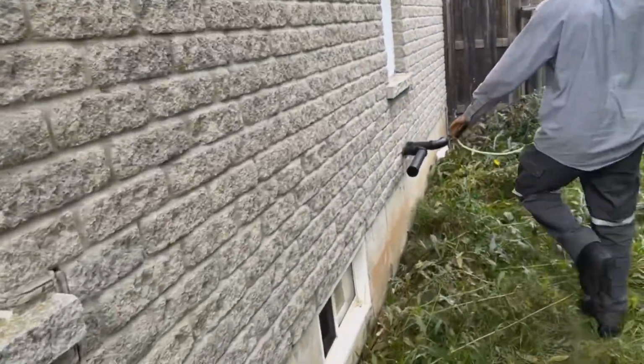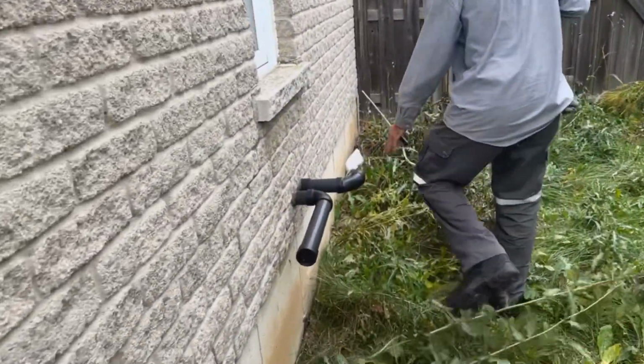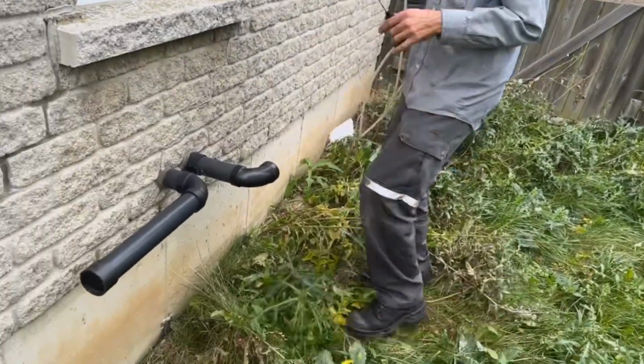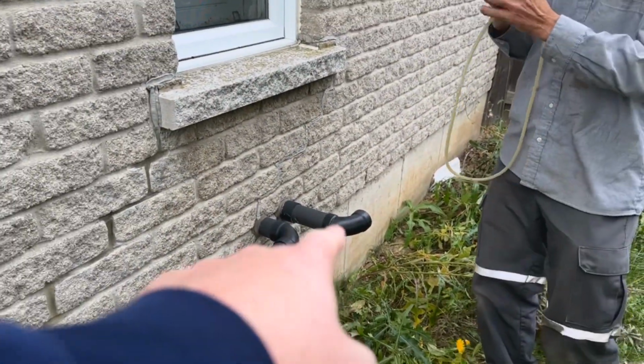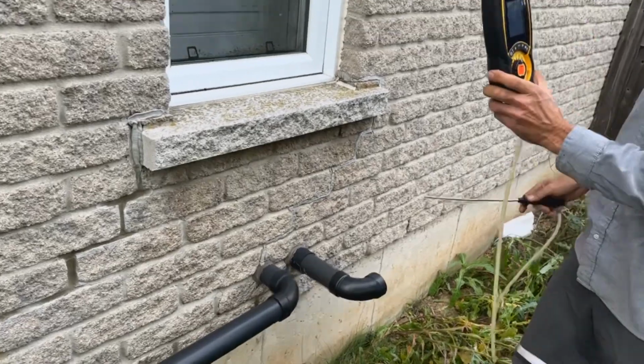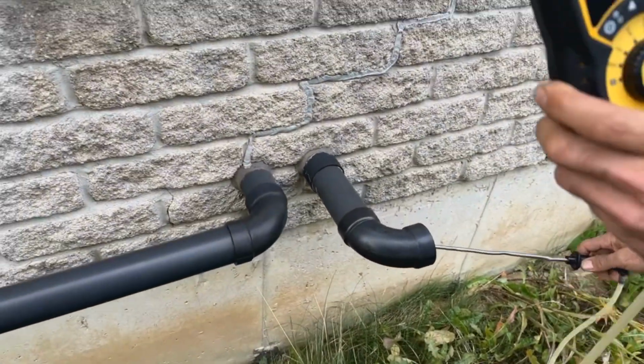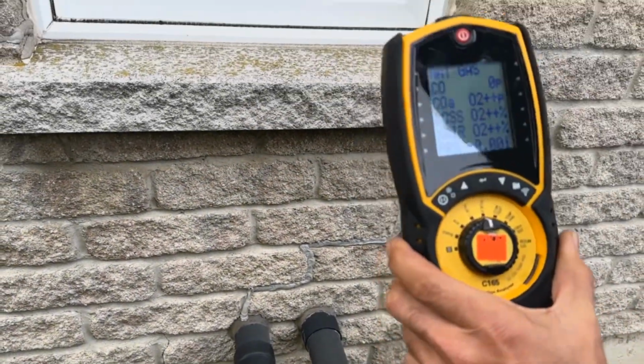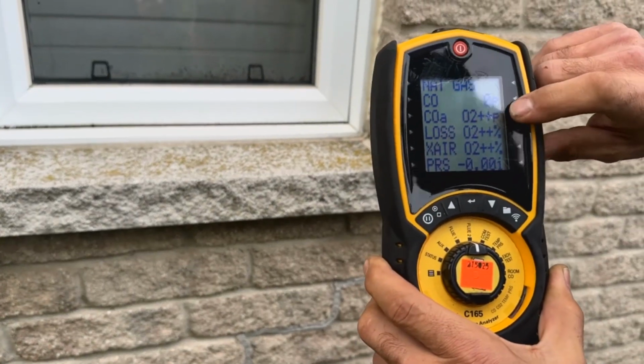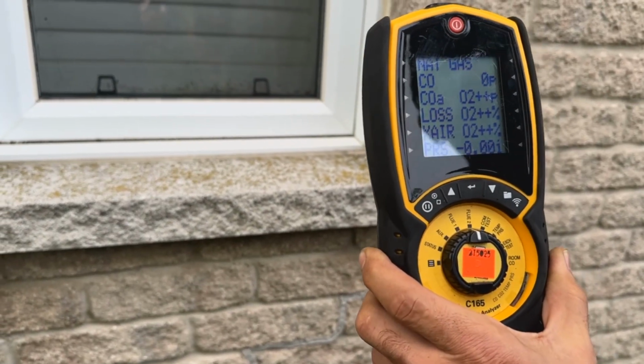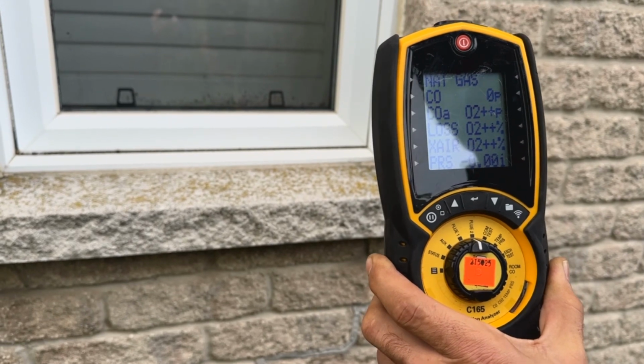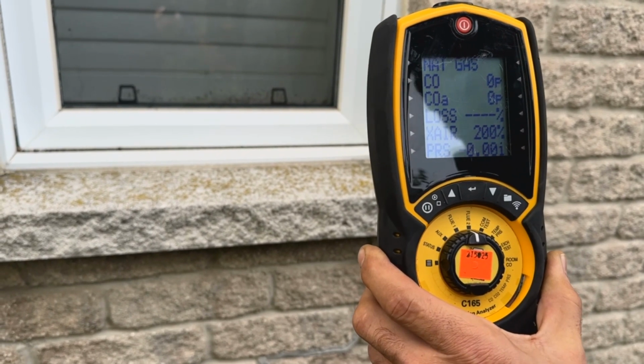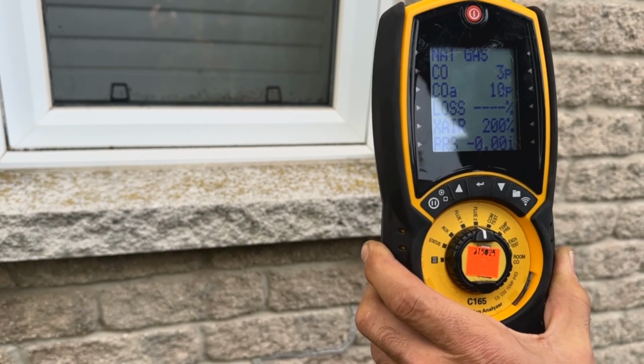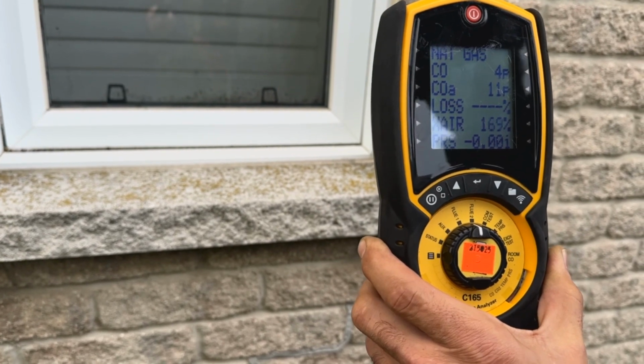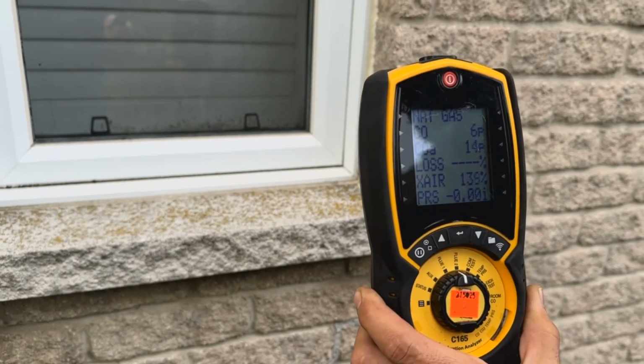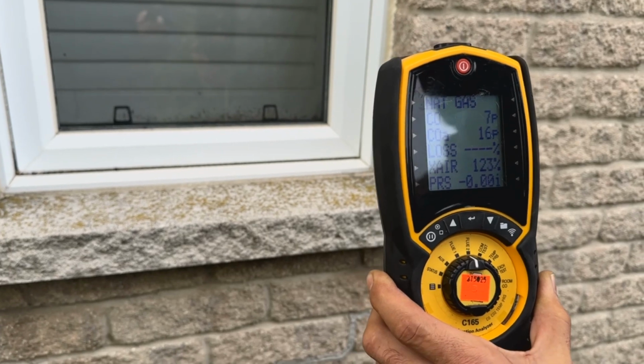Alright, so we got Paul here. Another way to check CO is at the vent itself. So you take your probe right into the exhaust, and we look for the CO reading. That number there, don't worry about the second one. As long as that CO stays under 100, then we're all good. I don't think we're defective yet. If it was, that thing would be spinning like a slot machine.